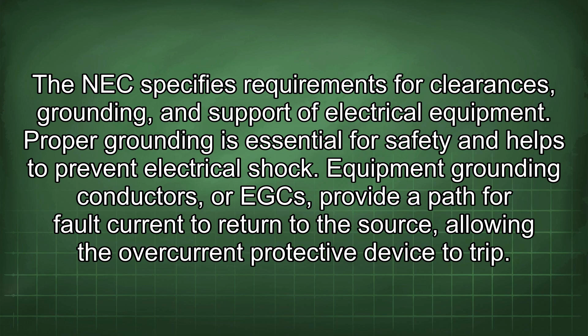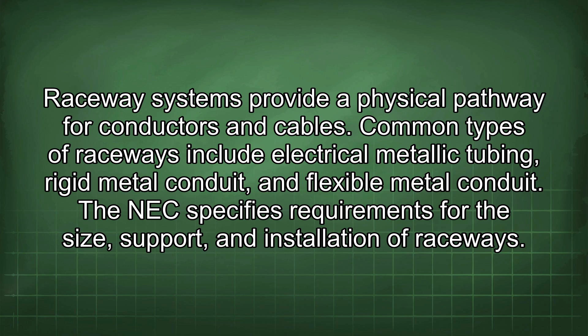Raceway systems provide a physical pathway for conductors and cables. Common types of raceways include electrical metallic tubing, rigid metal conduit, and flexible metal conduit. The NEC specifies requirements for the size, support, and installation of raceways. The fill capacity of raceways is also regulated to prevent overheating of conductors.